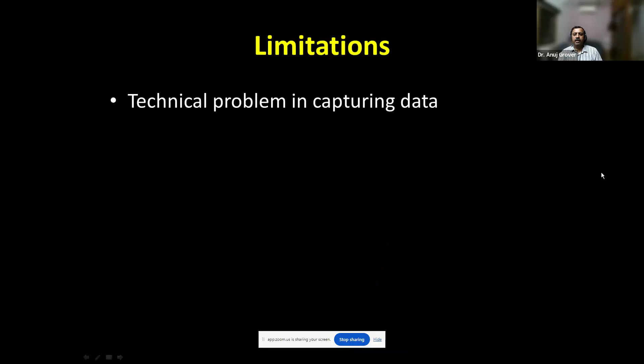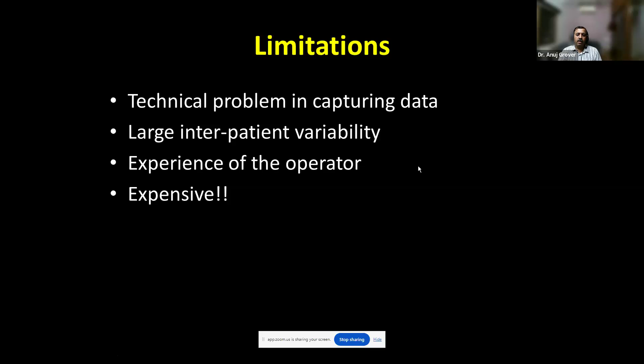So these are the scalars and the loops in detail. But one must remember that there are limitations of using any equipment. There can be technical problems. Your flow sensor may not be working appropriately. There could be interpatient variability. The operator may not be experienced, so you have to gain experience in looking at these graphs. And there is an expense attached to the flow sensor as well. If you're using a disposable one, it's fairly expensive.